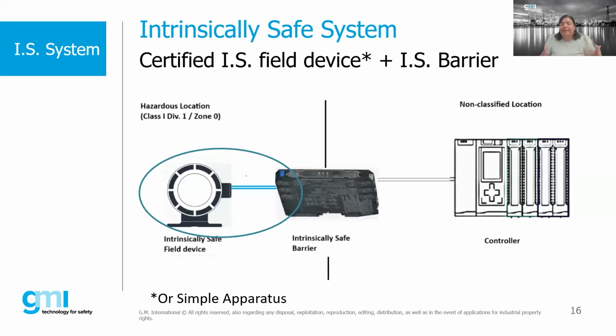So how do we achieve all these amazing things about intrinsic safety, this live maintenance, this flexibility for the wiring methods to be utilized? Well, intrinsic safety is, I think, the only protection method that is actually a system. It cannot exist by itself. So you're going to create an intrinsically safe loop. For that, you need to have an intrinsically safe certified field device connected to an intrinsically safe barrier, or the right name, associated apparatus. Then these two work together and create this intrinsically safe loop. So all that energy going into the field is being controlled, and we can ensure that even if you have a short circuit, you don't have a spark hot enough to react with the specific atmosphere where you're installing the device.